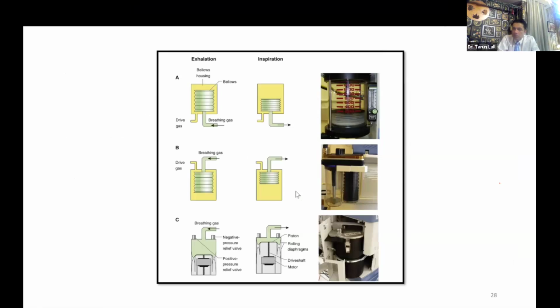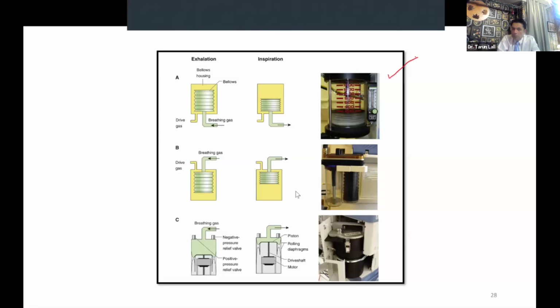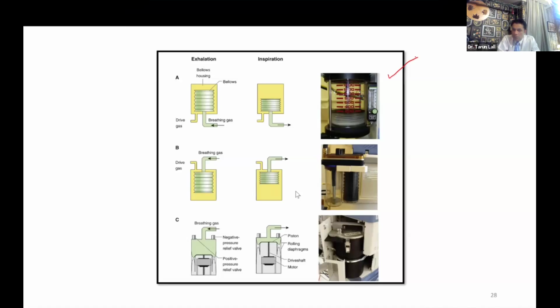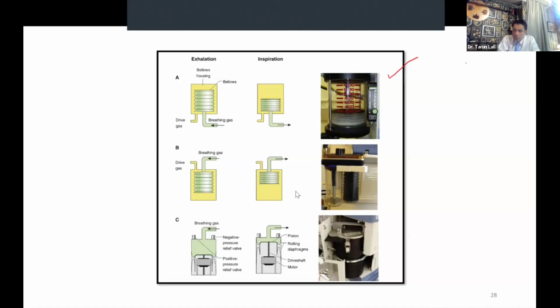The common ventilator that we see on most of our machines is this ascending bellows machine. The nomenclature is basically the direction in which the bellows fills up. How the bellows works is that this is classically called a bag in bottle. If you imagine the bag that we were using in the anesthesia machine, and you were using external force to compress it. So in this ventilator, your fresh gases fill up the bag from inside, and from outside, we have this airtight bellows housing.